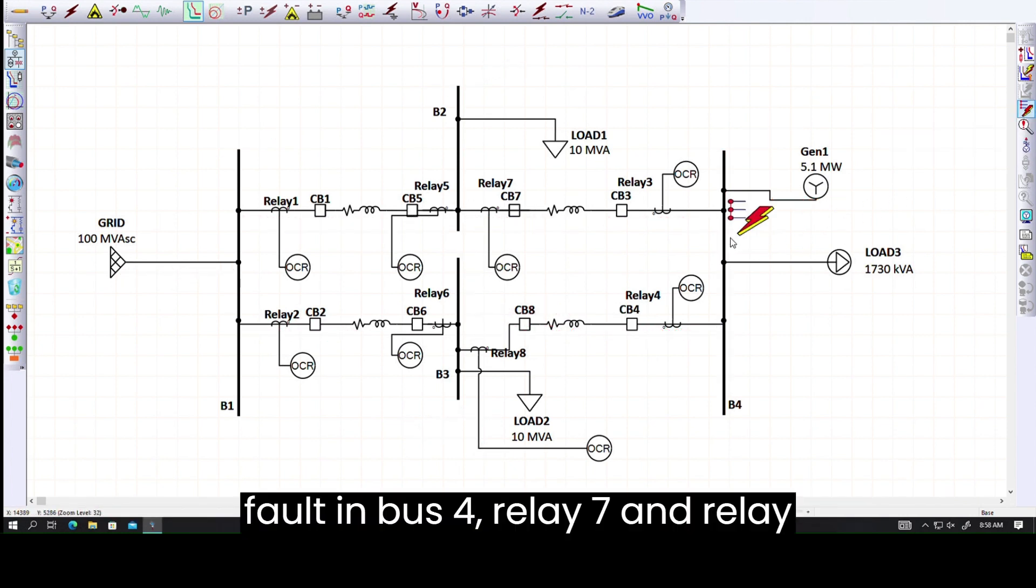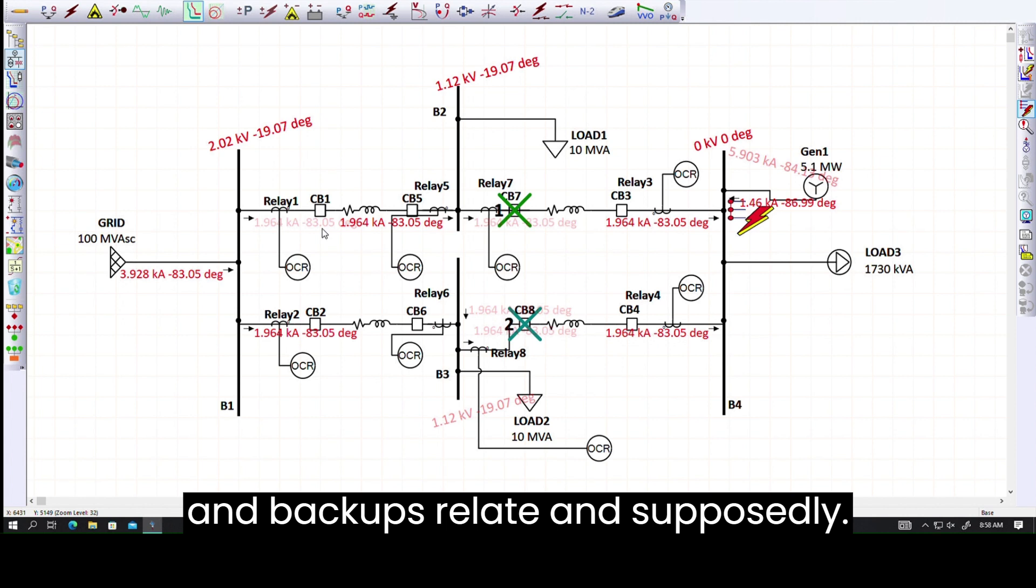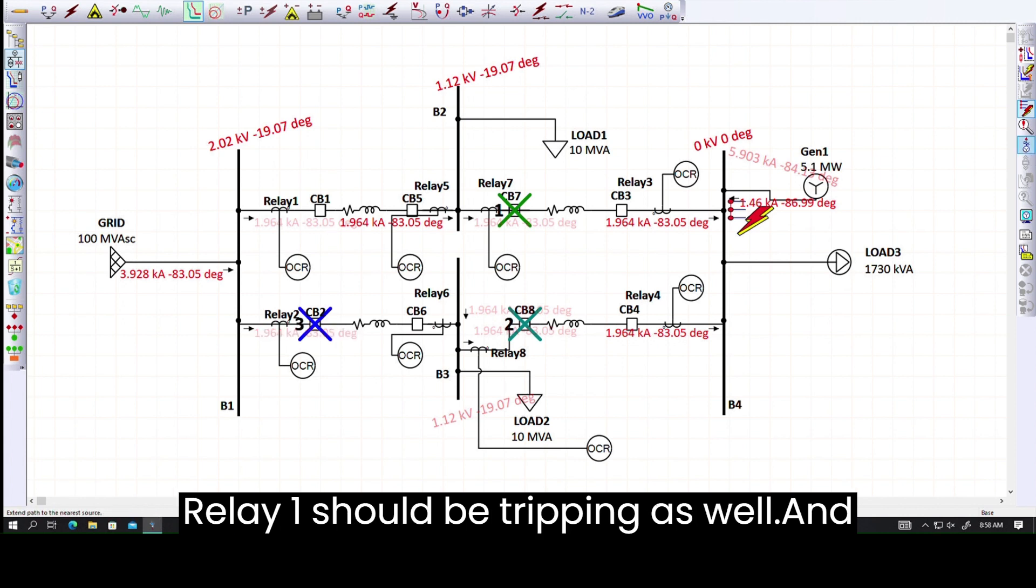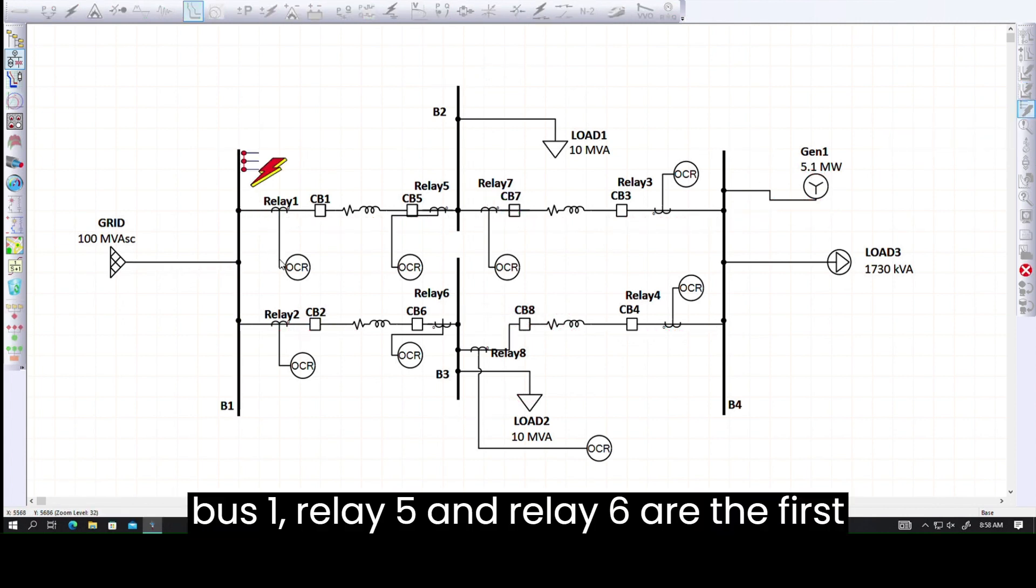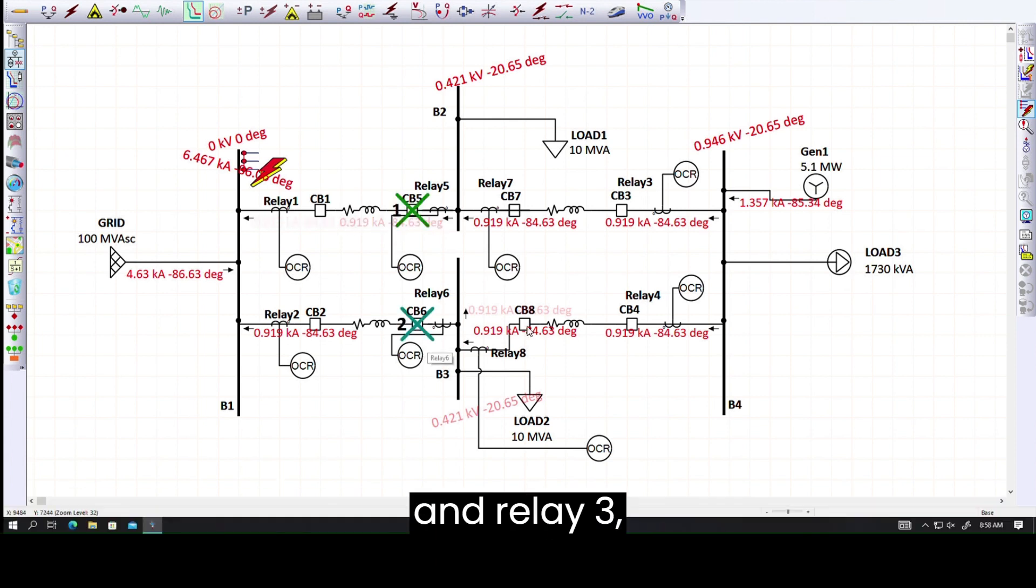Now if I put a fault in bus 4, relay 7 and relay 8 are going to be the first ones to trip, and backup relays 2 and supposedly relay 1 should be tripping as well. If I put a fault in bus 1, relay 5 and relay 6 are the first ones to trip, and backup relays 3 and 4 should be tripping as well.